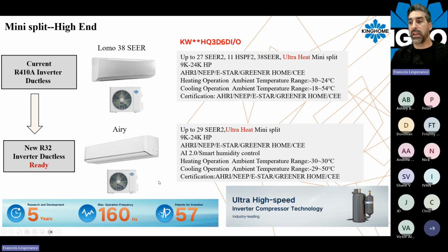This unit is the first one to be equipped with the new ultra high speed compressor, brand new on the market. It's made by Gree. It's been like 5 years of research and development to come up with this compressor. This compressor can operate with a maximum frequency of 160 hertz. So in comparison with other high frequency models, where most of them have a maximum frequency of 120 hertz, this is where the compressor gains more accurate performance and we can perform better. And so this is a good addition to the series to have this new compressor out on the market.